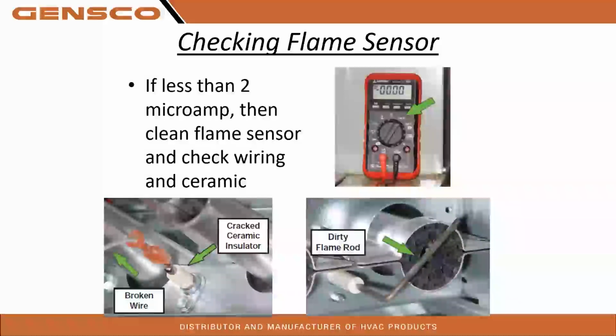Okay, so if less than 2 microamps, then clean the flame sensor, check wiring and the ceramic. Maybe we have a cracked ceramic isolator. Maybe we've got a broken wire. There is always a little bit of voltage on that rod. A lot of people don't understand that, but that's actually a rectification circuit. There is voltage coming down AC, I believe about 80 volts. As soon as it hits the rod and gets hot, it comes back as DC voltage, and AC and DC can pass over each other on the same wire. So the furnace board is looking for that DC callback.